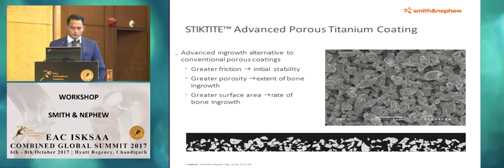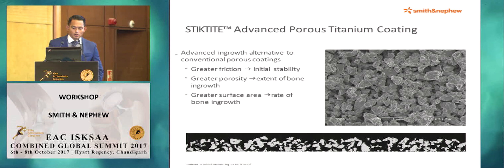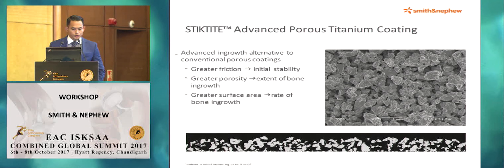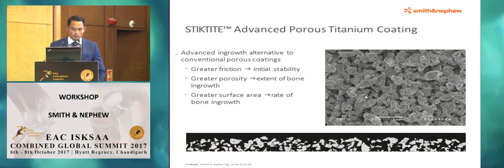StikTite is an advanced in-growth alternative to conventional porous coating. Compared to traditional conventional porous coating, there's greater friction for better initial stability, greater porosity leading to potentially increased bone in-growth extent, and greater surface area for a higher rate of bone in-growth. Here's an example of what it looks like under electron microscope.